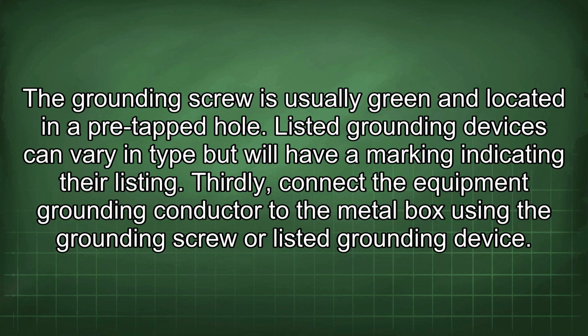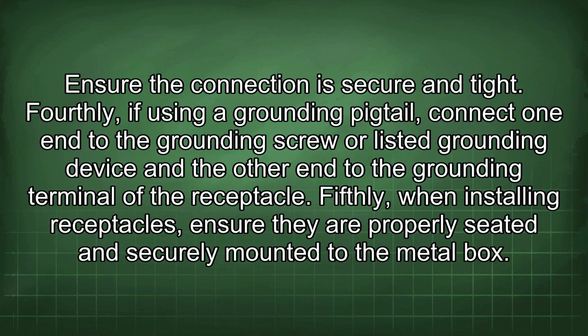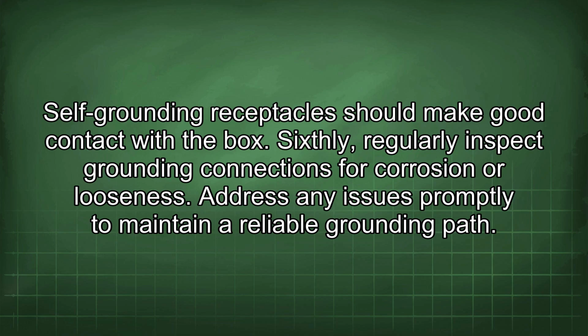Thirdly, connect the equipment grounding conductor to the metal box using the grounding screw or listed grounding device. Ensure the connection is secure and tight. Fourthly, if using a grounding pigtail, connect one end to the grounding screw or listed grounding device and the other end to the grounding terminal of the receptacle. Fifthly, when installing receptacles, ensure they are properly seated and securely mounted to the metal box. Self-grounding receptacles should make good contact with the box. Sixthly, regularly inspect grounding connections for corrosion or looseness. Address any issues promptly to maintain a reliable grounding path.